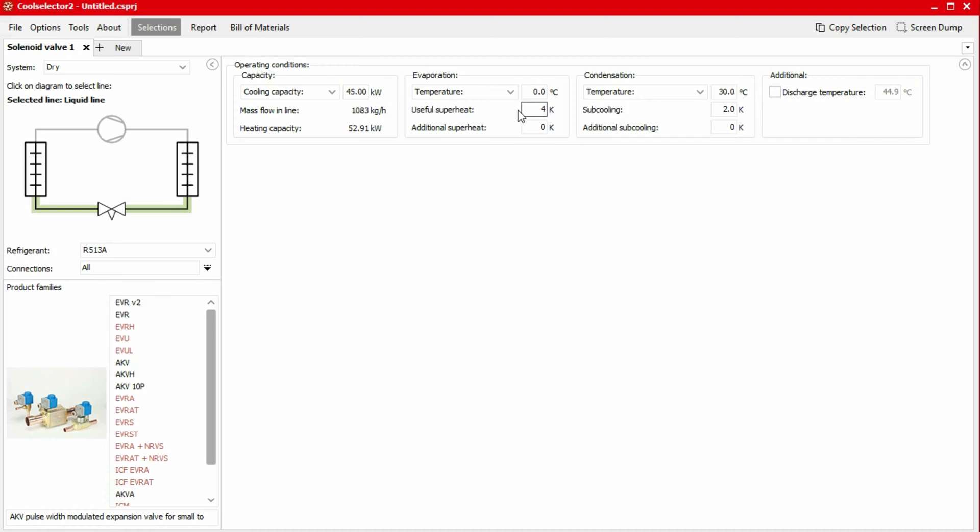We'll set a cooling capacity of 45 kilowatts, an evaporation temperature of 0 degrees Celsius with a useful superheat of 4 Kelvin. Then we'll set a condensation temperature of 42 degrees Celsius with a sub-cooling of 2 Kelvin. Then we can select the family of the solenoid valves.